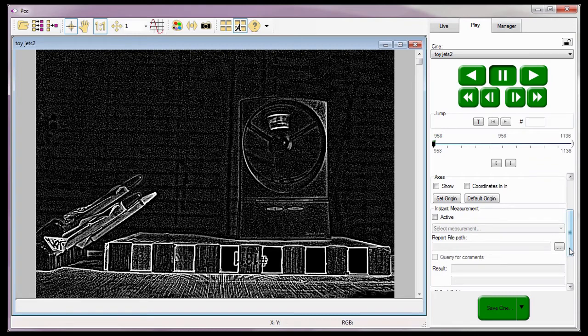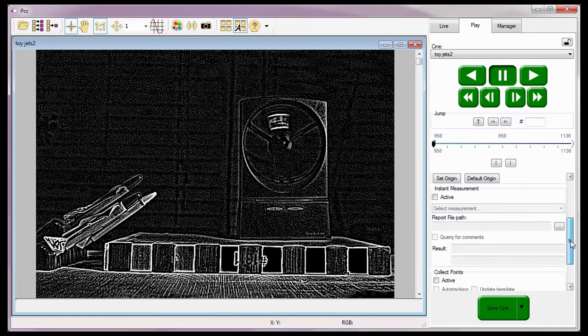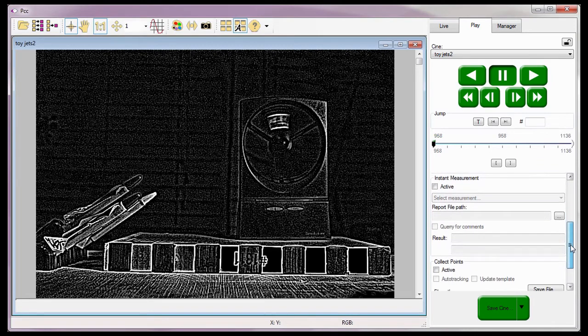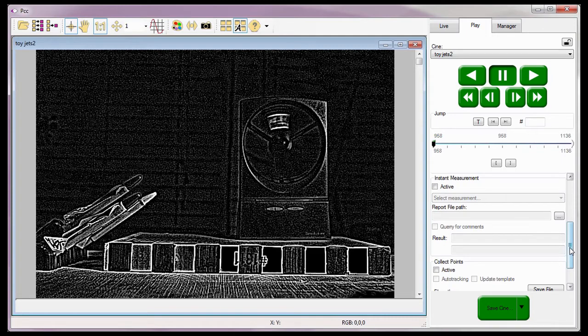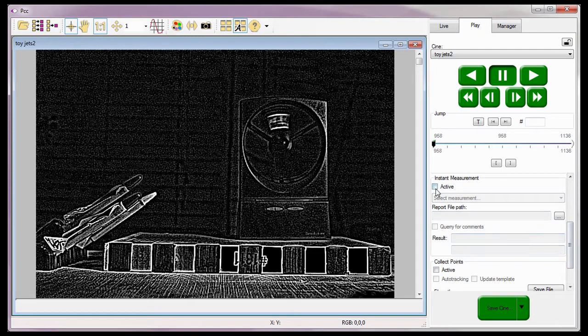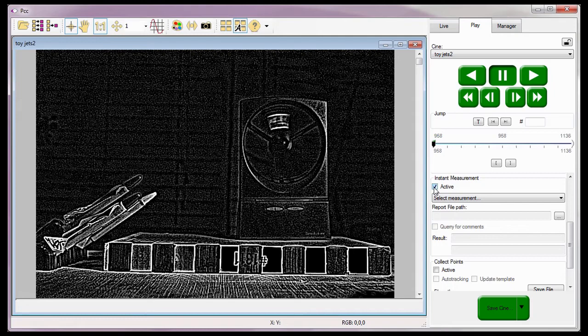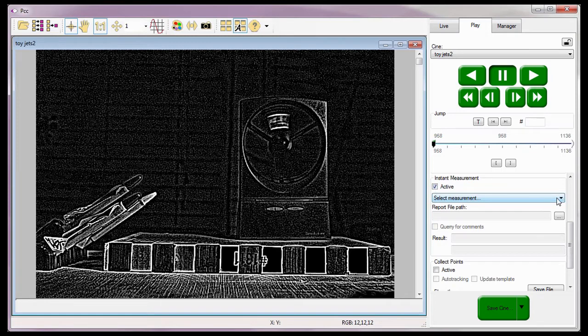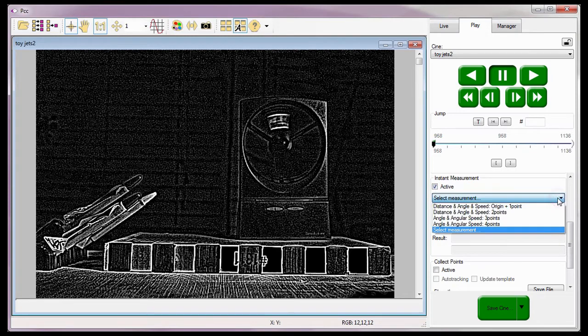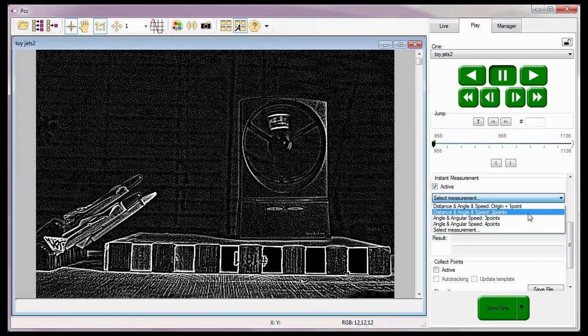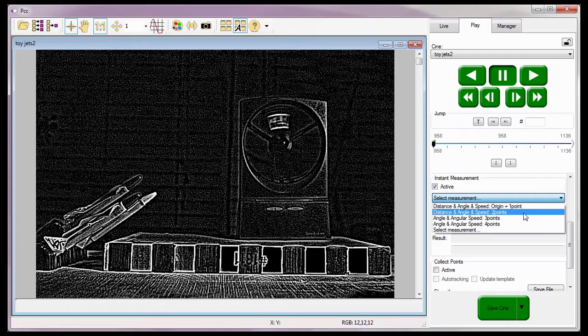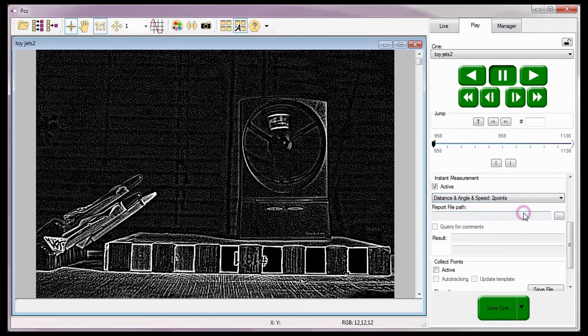Okay, I can now start performing distance, angle, and speed two-point measurements. In order to select the type of instant measurement I want to perform, I'll need to enable or check the active option in the instant measurement area. Activating the instant measurement option allows me to select, from the pull-down selection list, the type of measurement I want to perform. In this case, the distance, and angle, and speed two-point measurements.